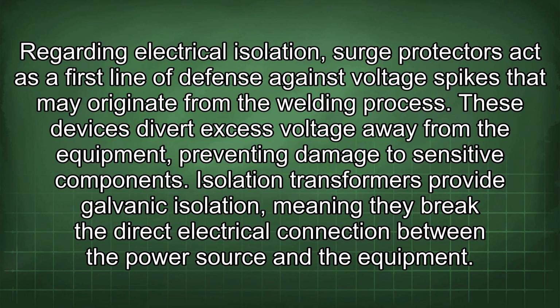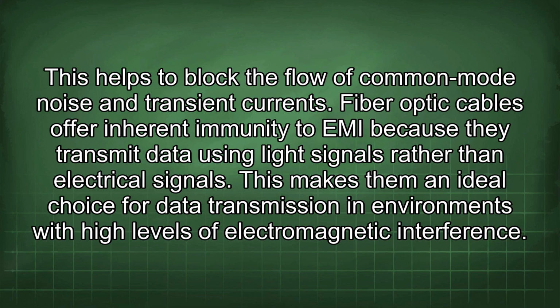Regarding electrical isolation, surge protectors act as a first line of defense against voltage spikes that may originate from the welding process. These devices divert excess voltage away from the equipment, preventing damage to sensitive components. Isolation transformers provide galvanic isolation, meaning they break the direct electrical connection between the power source and the equipment. This helps to block the flow of common mode noise and transient currents.